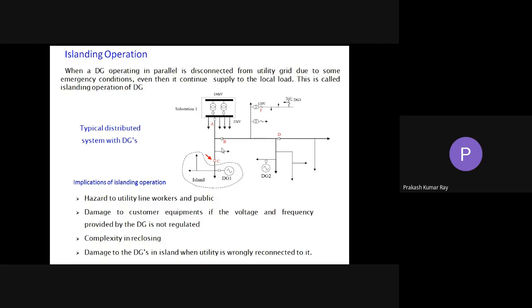Maybe the load will be damaged, otherwise the system will be damaged. So we should know when the DG is disconnected from the grid. We should properly detect, by using some efficient technique, that islanding has occurred, and accordingly the control aspect in the isolated system or island system should be activated, so that the frequency, voltage, and power requirement to the load will be maintained.